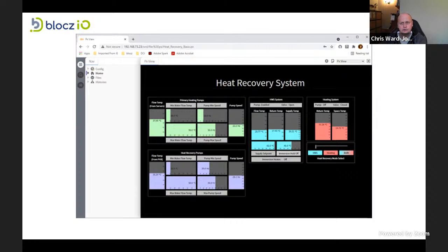You can increase the heat in your servers if you want to recover and repurpose more of it. You can slow down the variable speed pumps on one side of the circuit or the other, so one side of the heat exchanger gets hotter than the other. You may be pulling less heat out of the IT due to lower workloads but still want a higher heat output for your heating, etc. All of that is completely customizable and automated, done with a mouse click. It's really simple. Yes, it does work, and you can apply this technology really easily.